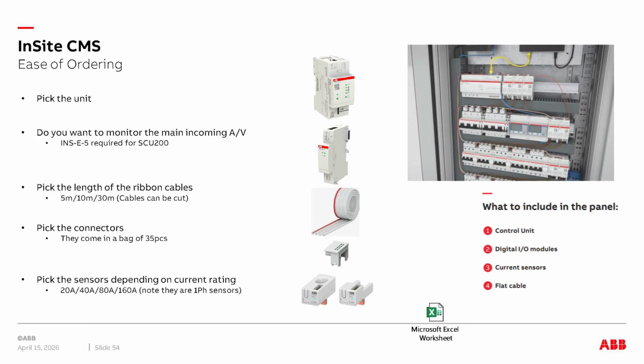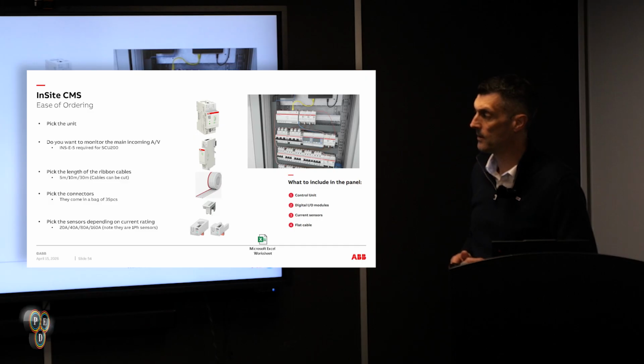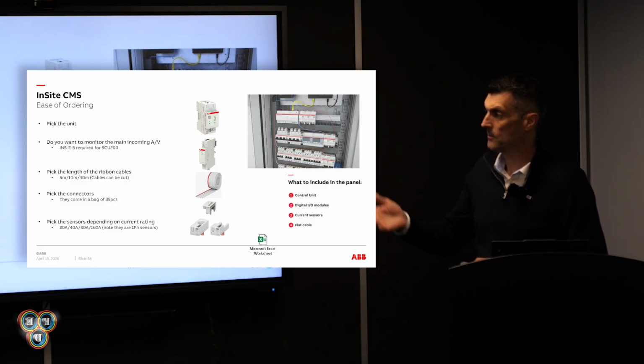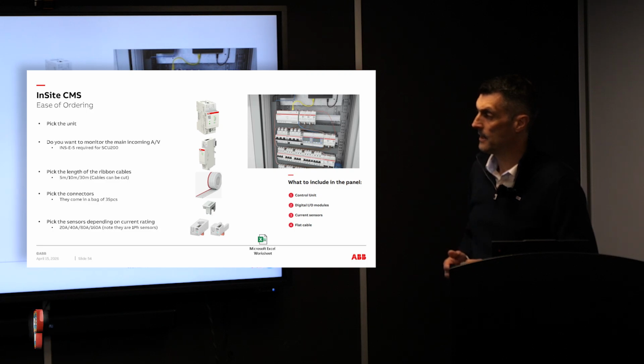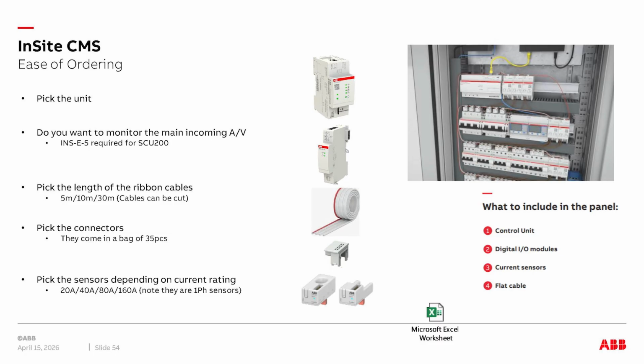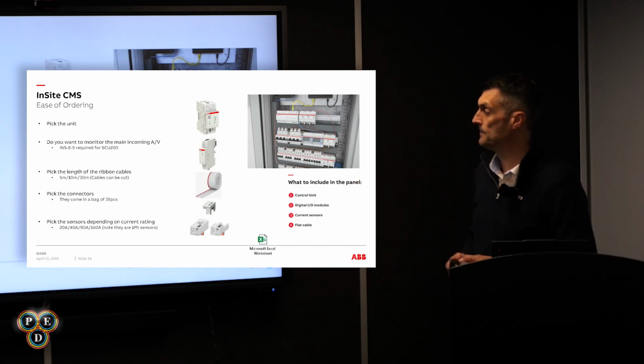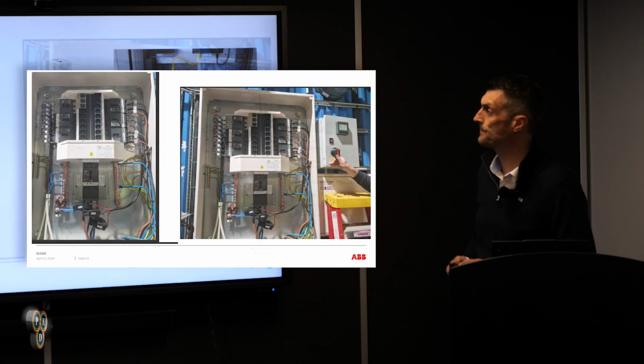Putting a bill of materials together is quite simple. You just need to pick a control unit, SCU 100 or 200. Decide if you want to pick up the main incoming supply, and if so, you'll need an expansion module for that. Pick the length of your ribbon cable, 5 to 30 meters, a bag of connectors, and then choose the rating of the sensor you want to use, whether open core or closed. We can send you an example part list so you can build a bill of materials from that too. Very simple in essence how you put it together.